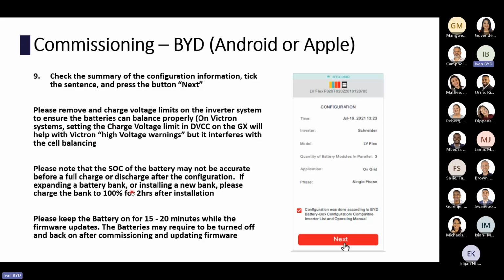Please note the SoC of the battery might not be accurate before a full charge. If expanding a battery bank or installing a new bank, please charge the battery to 100% for 2 hours after installation. And please keep the battery on for 15 to 20 minutes while the firmware updates. The batteries might require to be turned off and back on after commissioning. It's very rare, but that needs to be done.